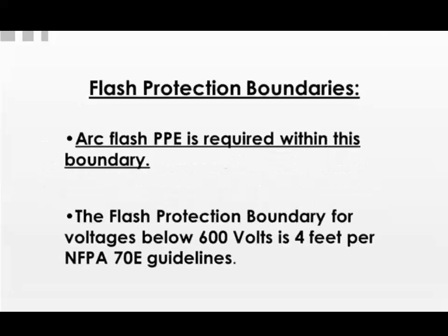All right, flash protection boundaries. Arc flash PPE is required within this boundary. So the flash protection boundary for voltages below 600 volts is 4 feet per NFPA 70E guidelines. So for work to commence, or an electrician working on a piece of equipment, they have to be properly outfitted with the right arc flash personal protective equipment. They've got to have the right training. They've got to have the right insulated tools, etc.